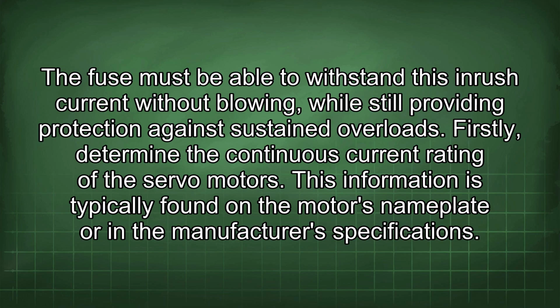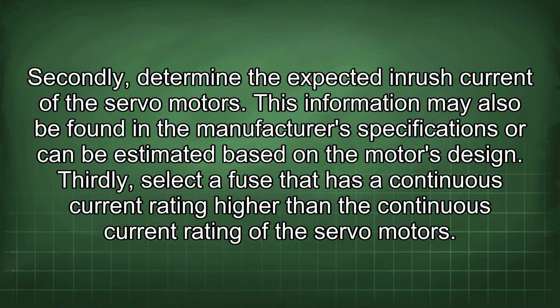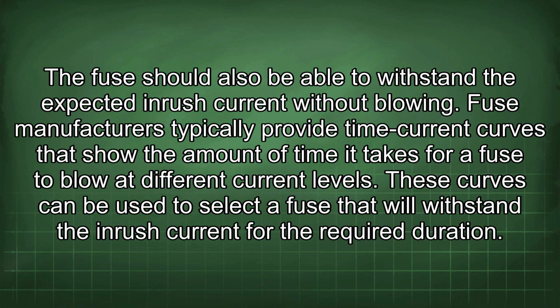Firstly, determine the continuous current rating of the servo motors. This information is typically found on the motor's nameplate or in the manufacturer's specifications. Secondly, determine the expected inrush current of the servo motors. This information may also be found in the manufacturer's specifications or can be estimated based on the motor's design. Thirdly, select a fuse that has a continuous current rating higher than the continuous current rating of the servo motors. The fuse should also be able to withstand the expected inrush current without blowing.